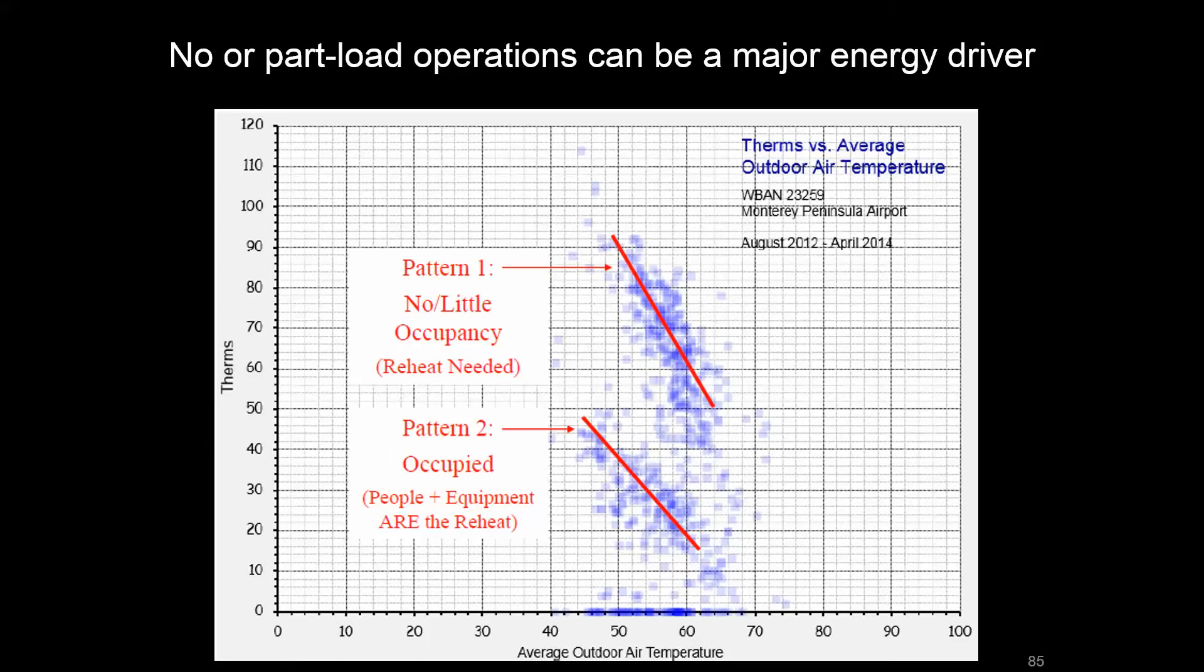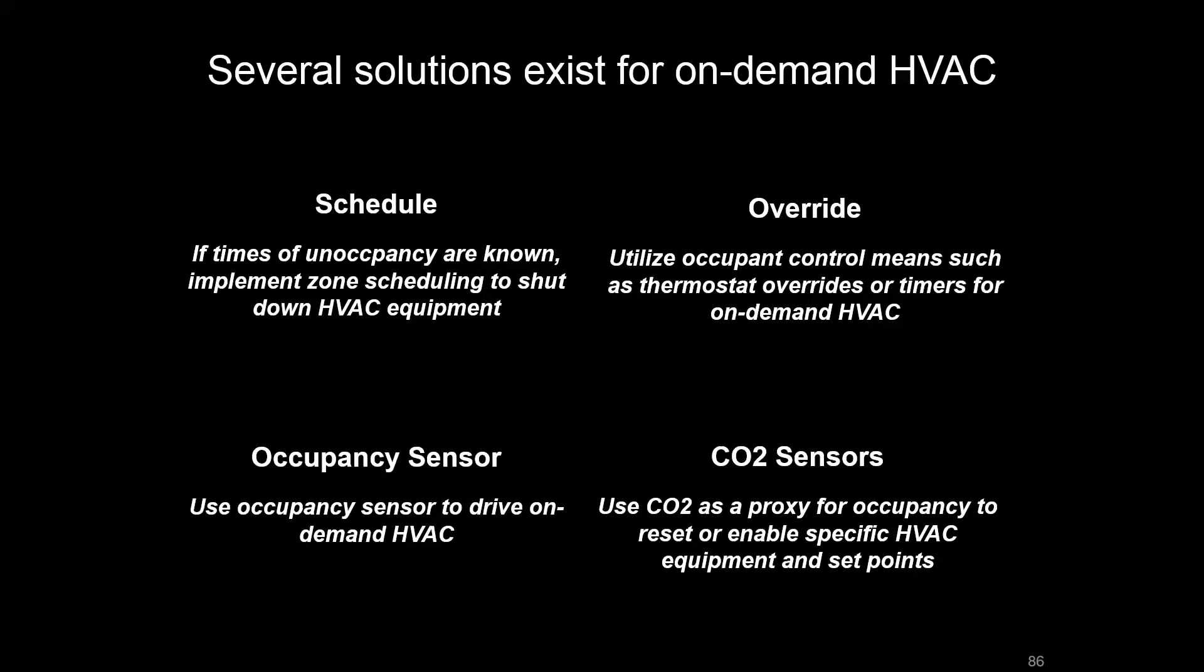One thing to keep in mind is that when you see no or part load operations, those can be a real major energy driver. And there are solutions for things like on-demand HVAC, where you have those really big swings from high load to no or low load. They could involve scheduling a space if you know the schedule, relying on something like an override at the thermostat, a push button for folks to engage their HVAC. There's ways that you can take an occupancy sensor and incorporate that into your automation system. Or something like CO2 as a proxy, and having that be an indication for what your load is, if your load is predominantly people-based.